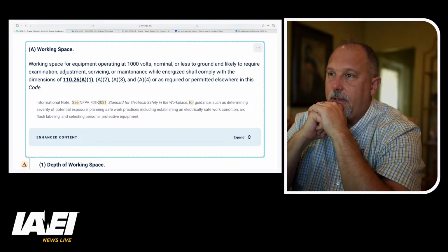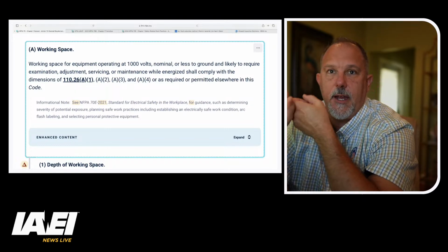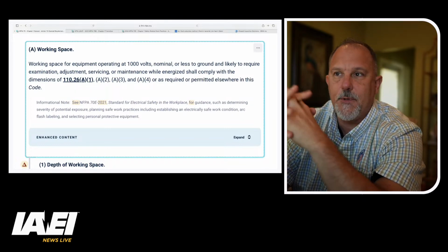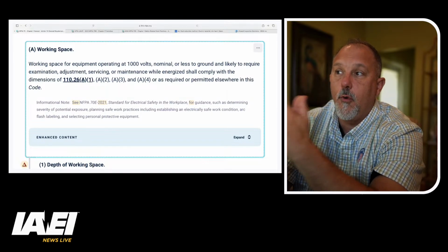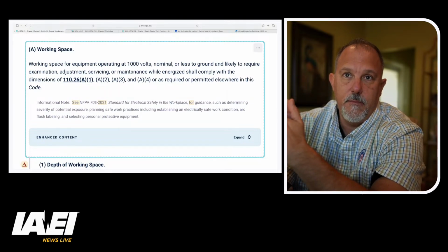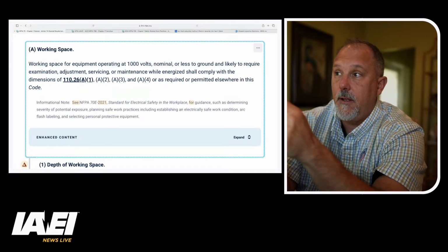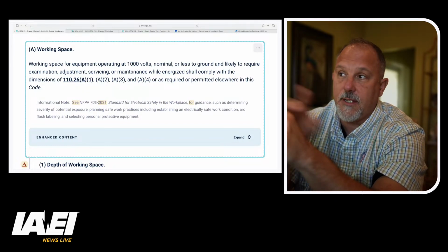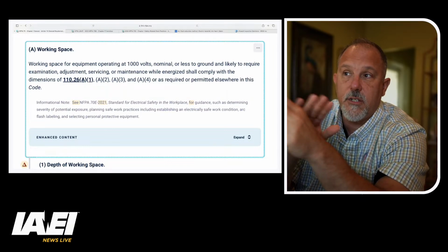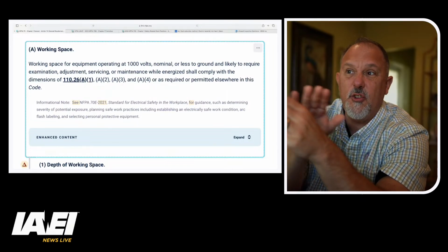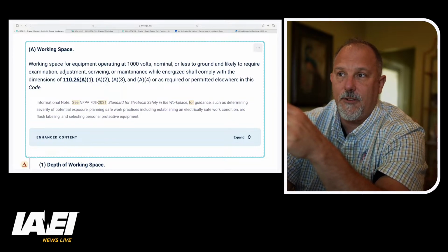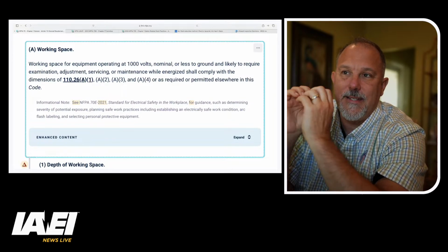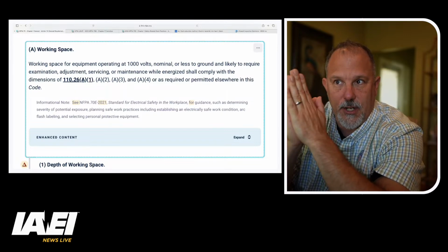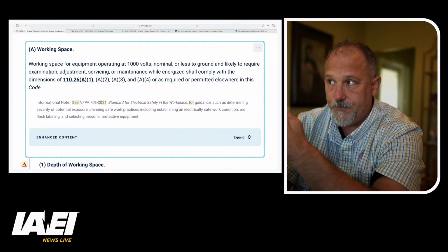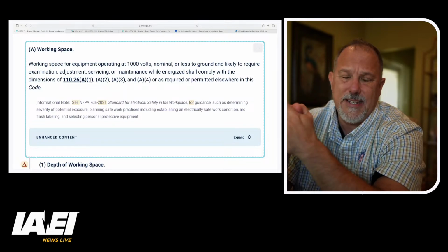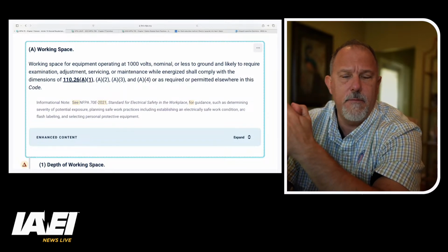Am I going to examine it, adjust it? I'm not going to adjust. I'll have to verify absence of voltage. I'm not going to be performing maintenance while it's energized. So I can strike that off, maintenance while energized. I can say I'm meeting that. I'm not servicing it while it's energized. I'm not doing any adjustments while it's energized. And I'm not going to do examination while energized, verifying absence of voltage. That wouldn't be examination. I'm doing a verification.